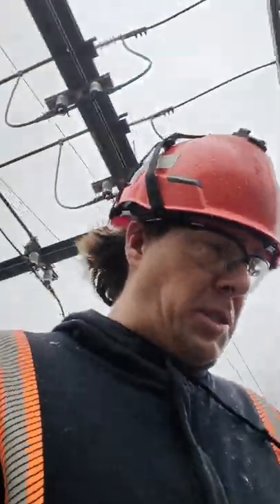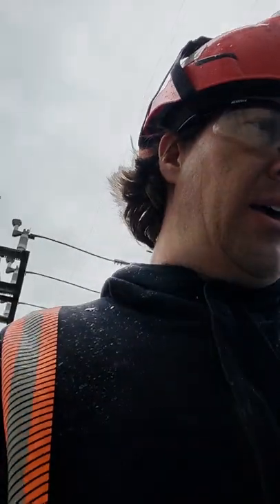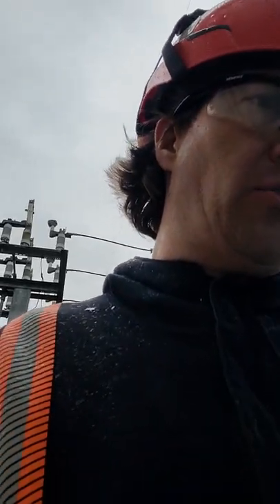Alright, so we've got 650 customers out of power. We're at the substation now. It was a branch — quite a large branch. Actually, it was the entire top of a tree that took out the recloser.